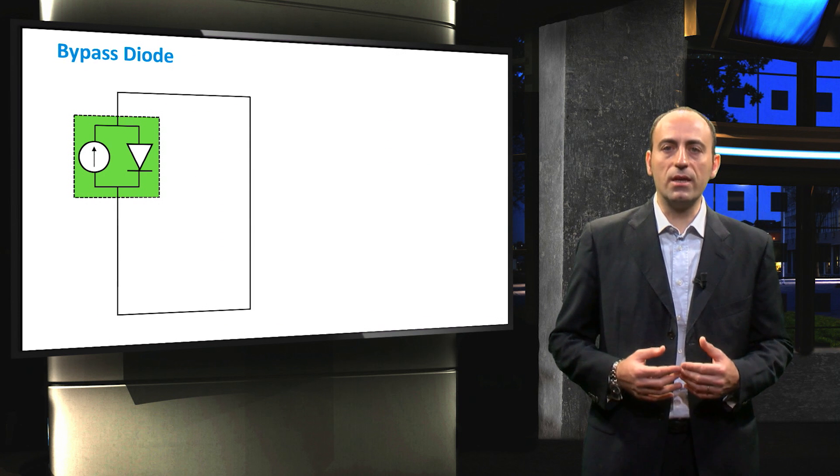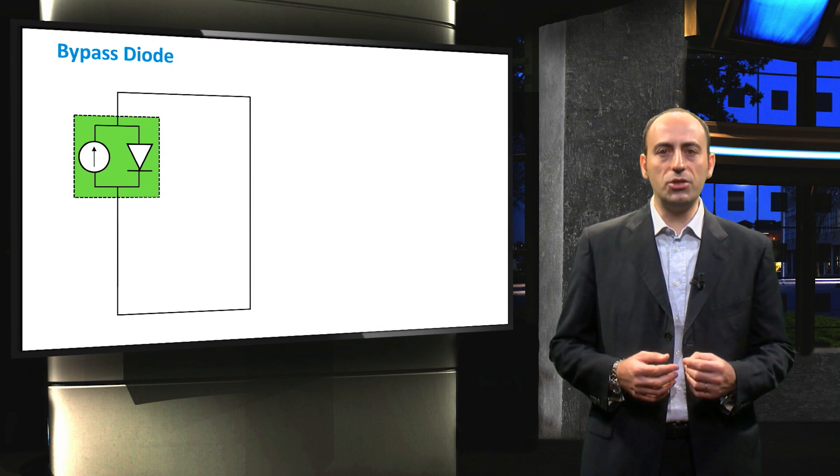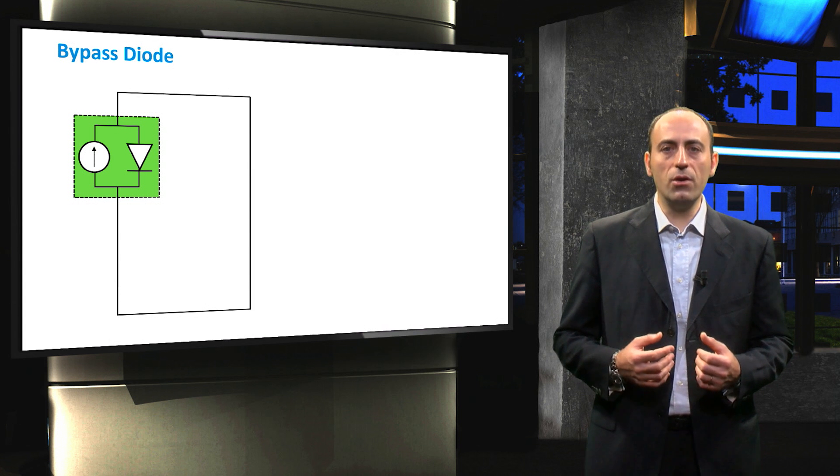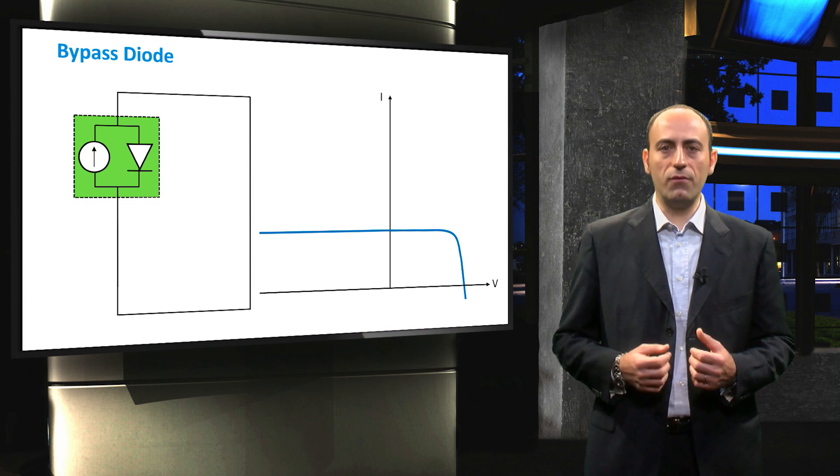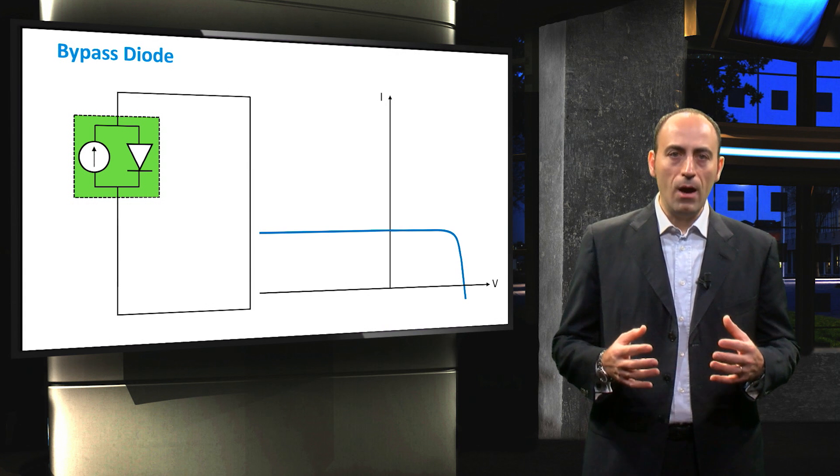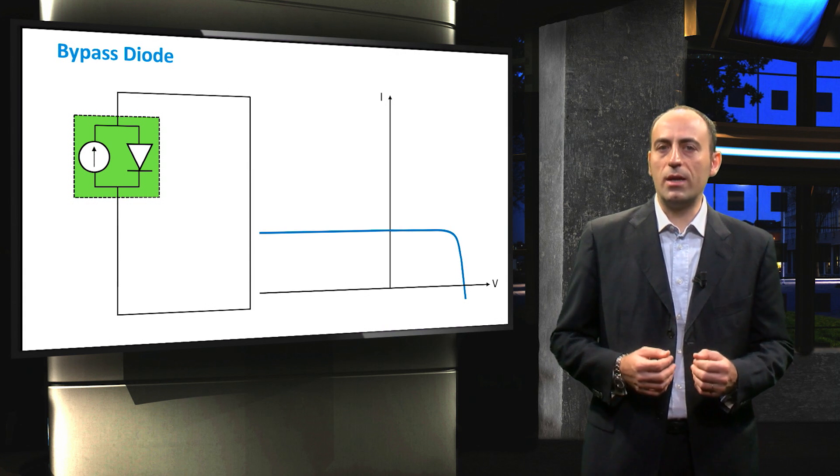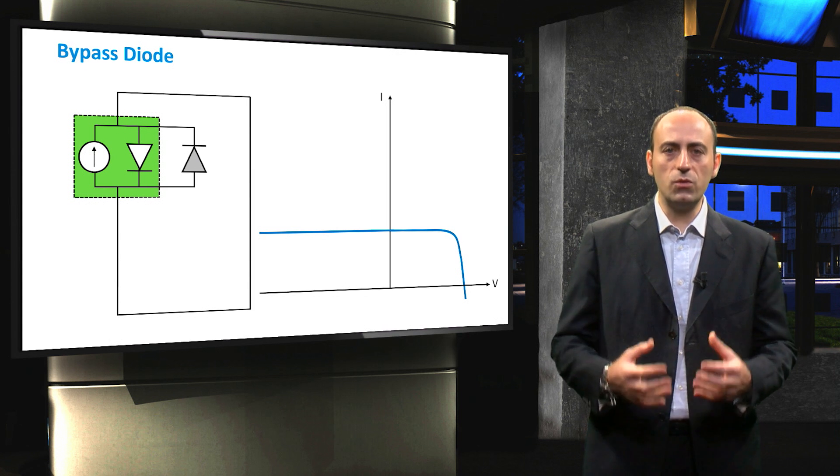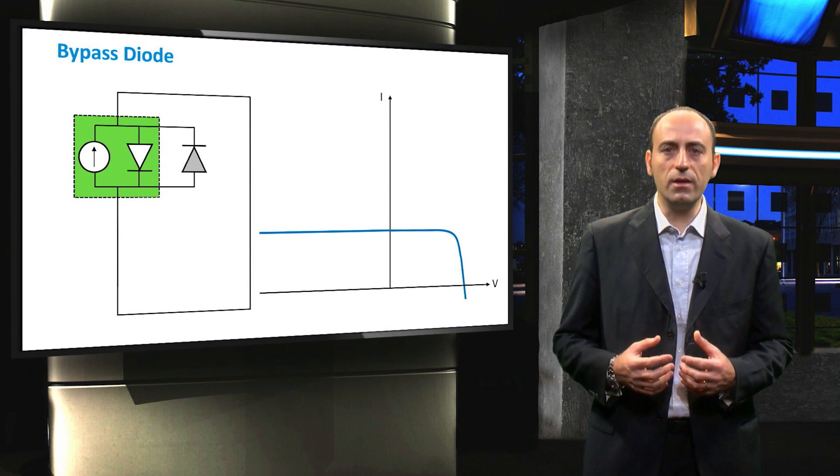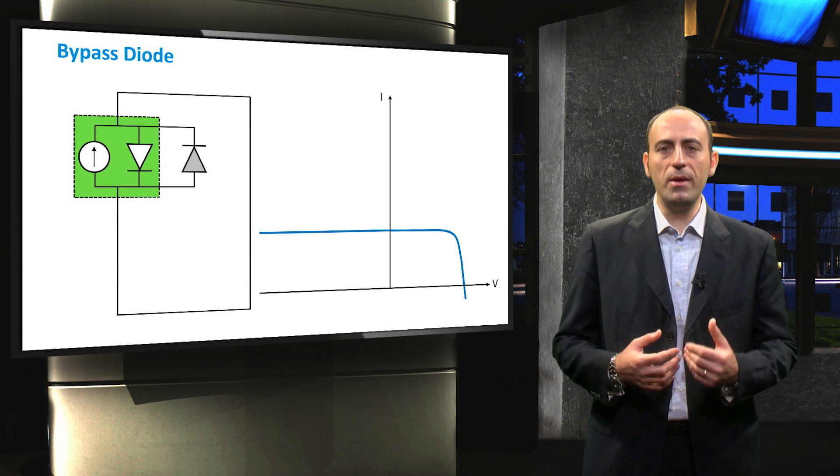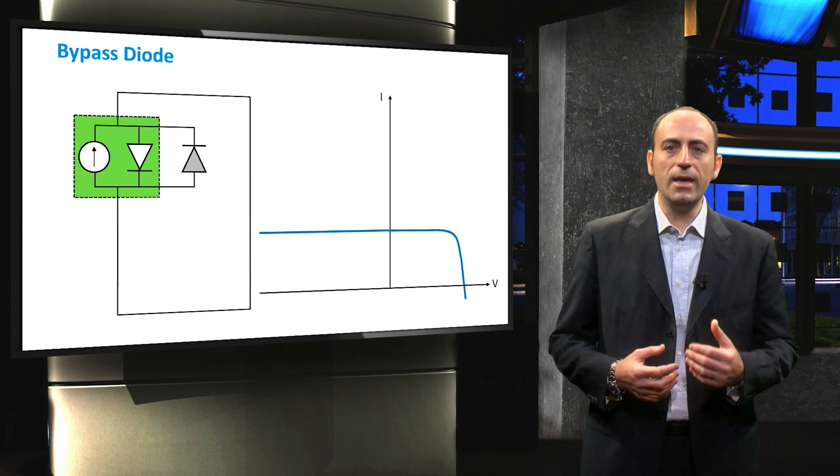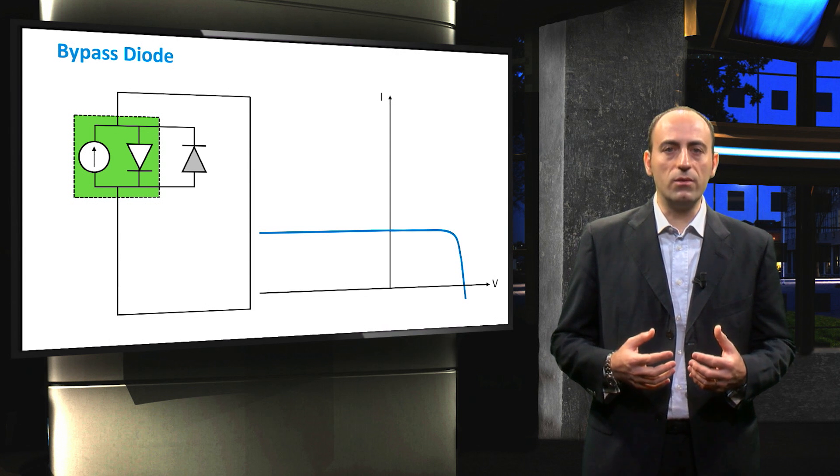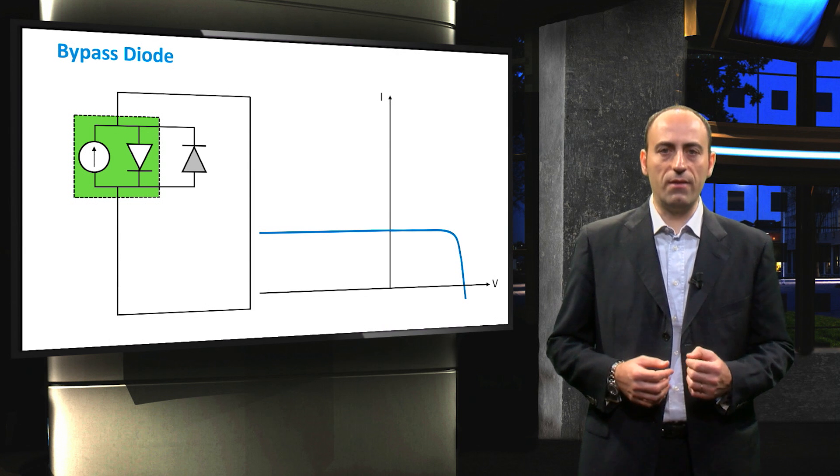As we have already seen, a solar cell inside a circuit is represented with a current generator and a diode in parallel. The corresponding IV curve is depicted in the graph on the right hand side. Now we are going to introduce an additional element called the bypass diode. Its role is to avoid the destructive effect of hotspot heating when a solar cell is dissipating power of other cells in case of current mismatch. Therefore, the role of a bypass diode is to preserve module integrity and lifetime.